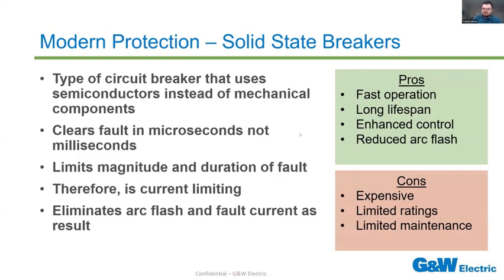So starting out, solid state breakers. This is a type of breaker that uses semiconductors instead of mechanical components. There are no mechanical components at all in this type of breaker. Because it relies entirely on the electronics, it clears those faults in microseconds instead of milliseconds. That is a fraction of an electrical cycle. That's going to limit the magnitude and duration of the fault almost immediately. Therefore, it acts as a current limiting device. And because it operates and clears so quickly, it's going to virtually eliminate arc flash and fault current from that fault as a result.